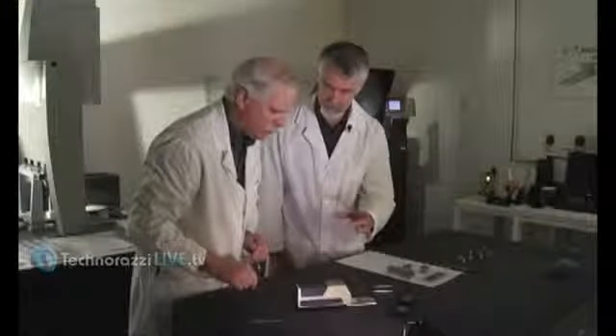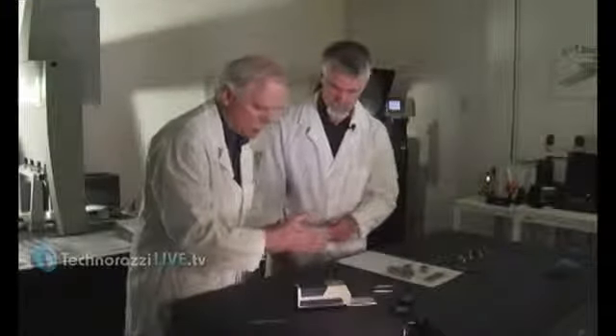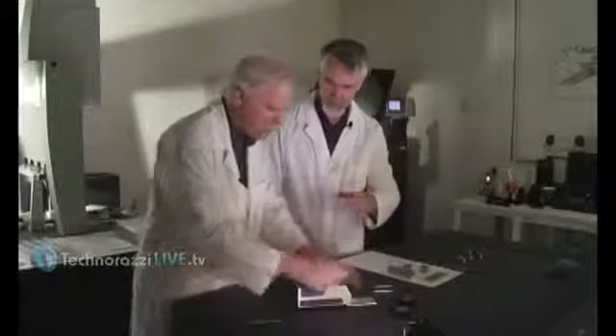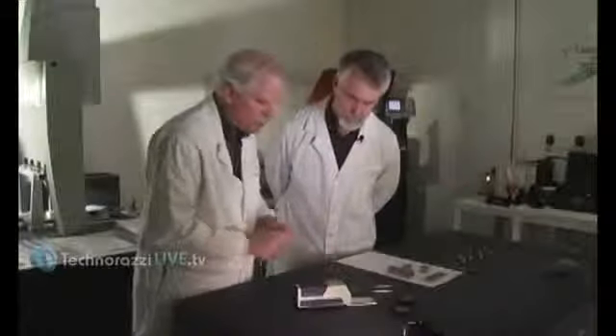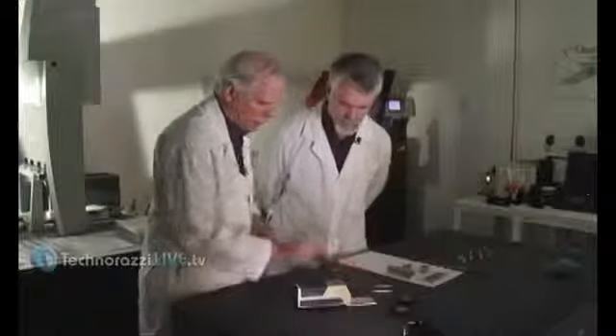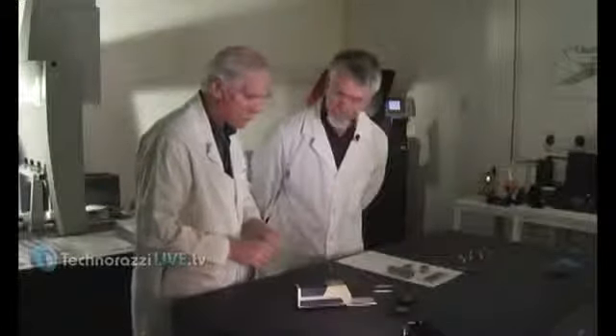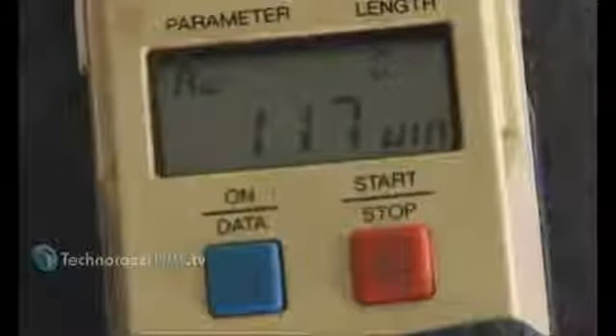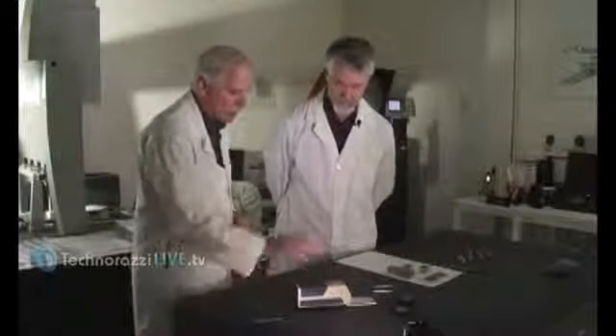So you rotated it a little bit. Just a little bit to the side. We'll go a little bit. So you're trying to find where the maximum reading comes from. A little less, so that means we're going the wrong direction. The highest number will be the true number for RA in this case. Anytime you change probes, you have to reset the gain. That's not a defect in the probe, just different probes have different impedance or whatever the case. Now we're set at 117, so this is now set for use.